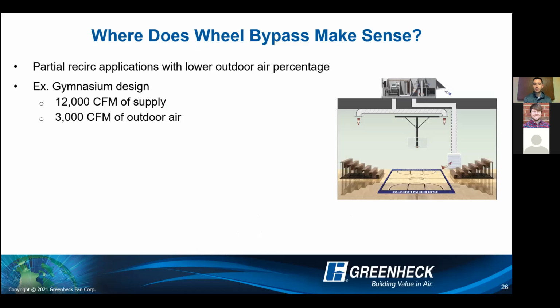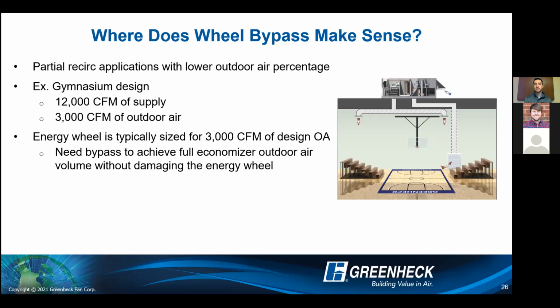Now, where does it make sense to use wheel bypass? So really any partial recirc applications where you have lower outdoor air percentage. So obviously you can still have lower outdoor air percentages and use energy recovery. In this example, we're looking at a gymnasium. Let's say we have 12,000 CFM of supply, 3,000 CFM of outdoor air, right? So the energy wheel is typically only needing to be sized for 3,000 CFM of that design outdoor air.